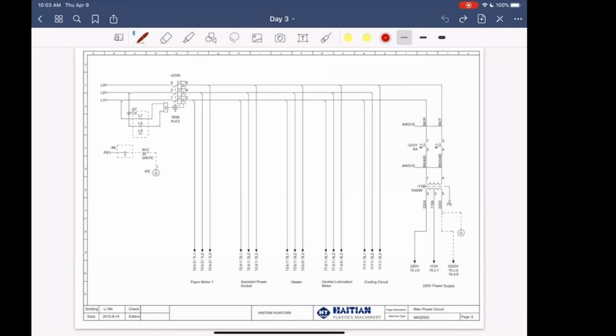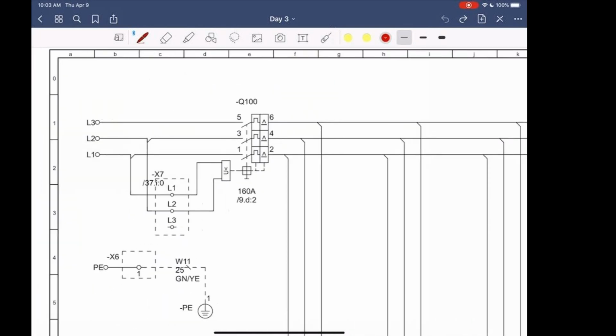And so we begin at page 9. Page 9 is the first page of the actual drawings. And so you'll see line 1, line 2, line 3. And that goes to Q100, which is the disconnect on the front of the machine. And that's a 160 amp disconnect. And this little guy, the U, is the shunt breaker, which is on the high side of the machine.